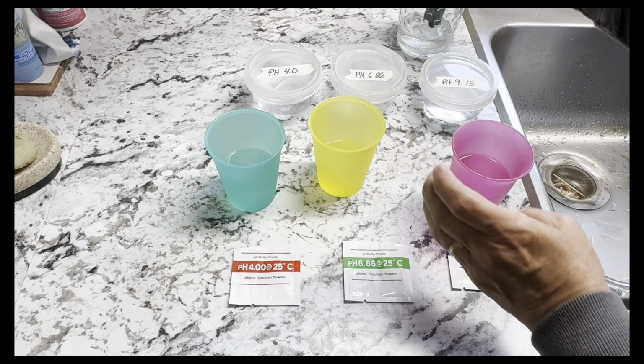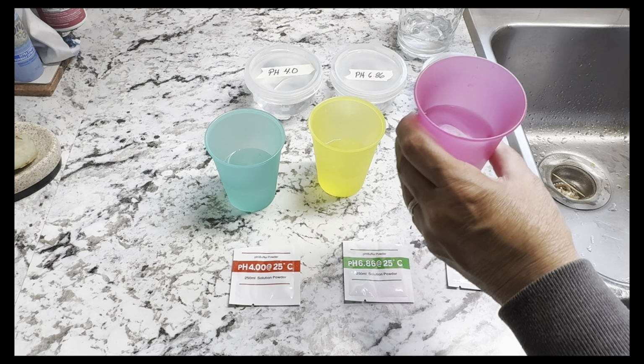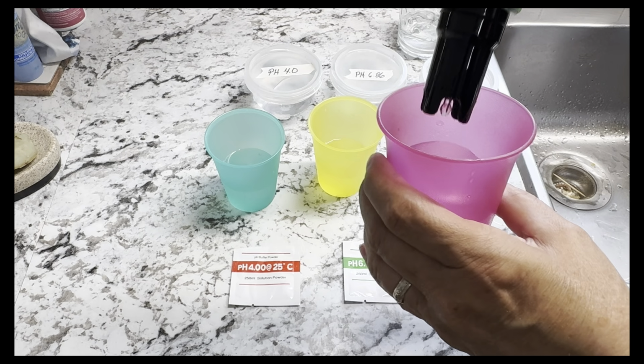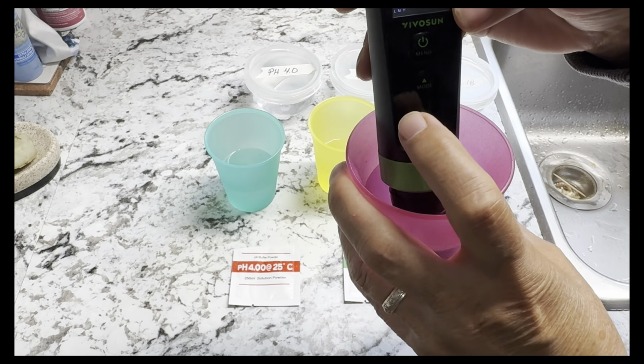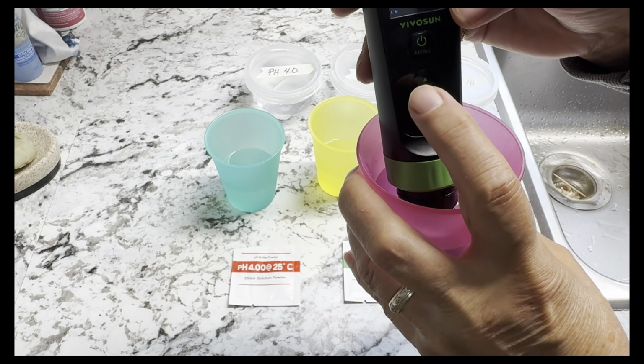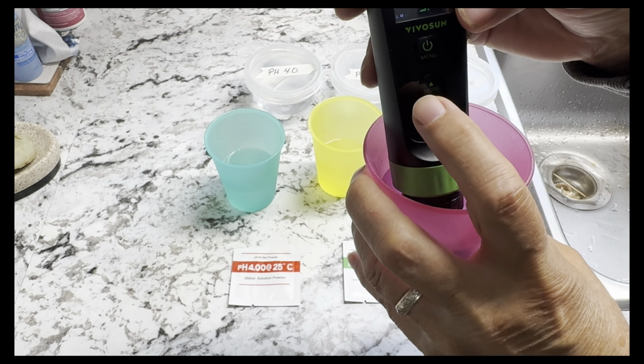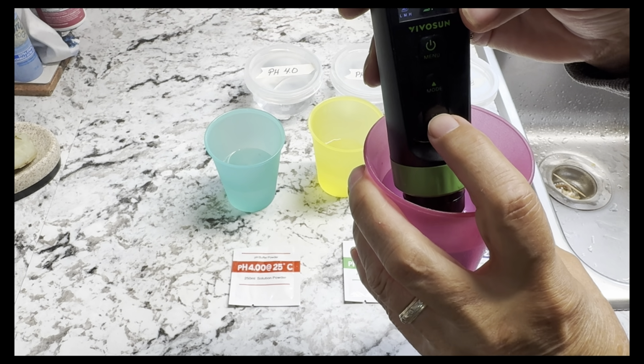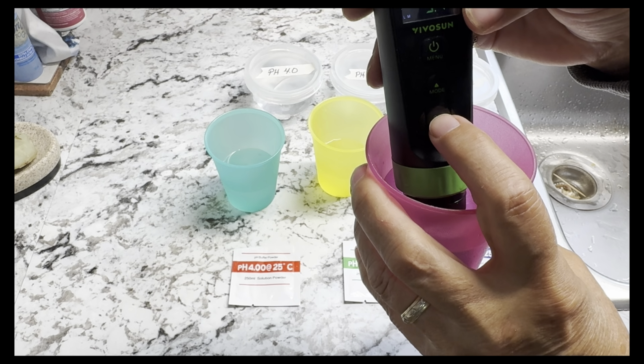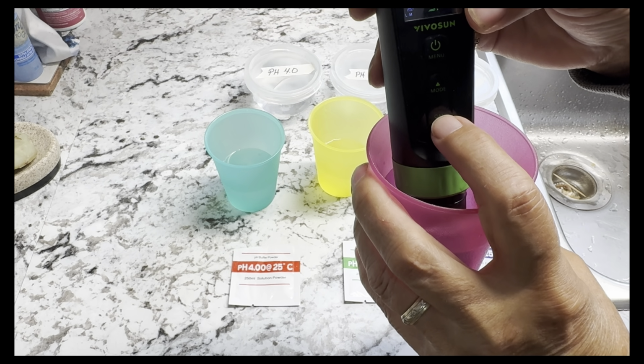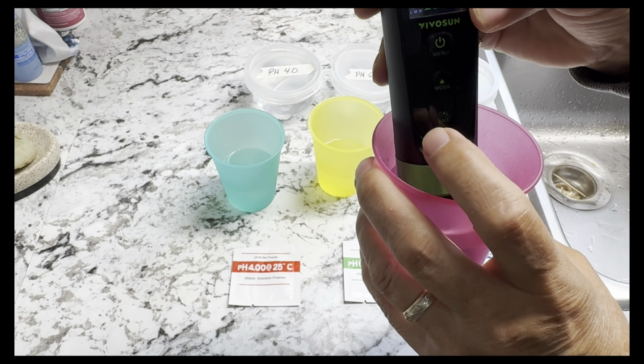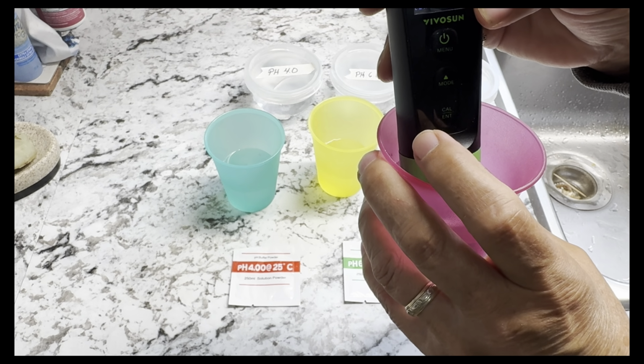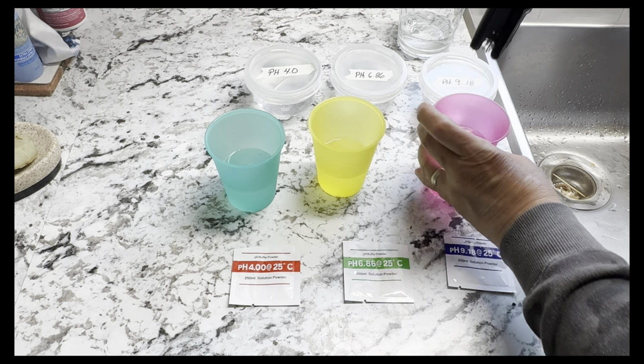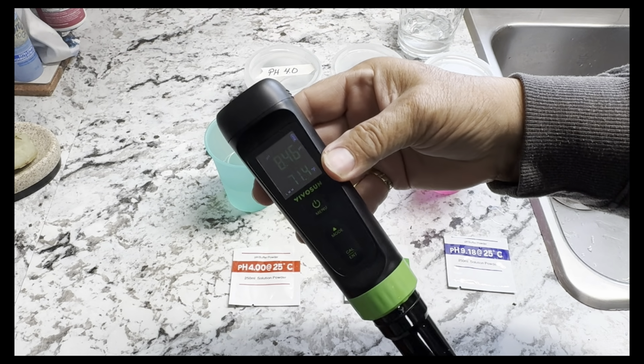Again, just give it another rinse, and you're ready to do the calibration at the 9.18. Again, that thing will start flashing. There'll be an H once it stabilizes and quits flashing. Just hit the calibrate button, happy face appears, and you are good to go. Your meter is now all calibrated.